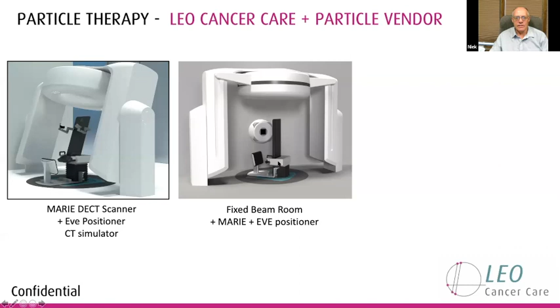But the machine can also pivot around this point and be used as an in-room CT scanner, or we're also developing a mobile gurney, in which case the scanner can be used as a standard CT simulator for supine scans. Important to note that this scanner is designed to give you a full dual energy CT scan. A typical dual energy CT scan takes significantly less than 1 minute. Compare that with the 30 to 45 minute scan time of the previous generation scanners. That's a huge improvement. I do have to re-emphasize that this is a scanner developed for upright radiation therapy treatments, but we can of course also use it for diagnostic scanning of pulmonary and thoracic patients who have breathing problems.